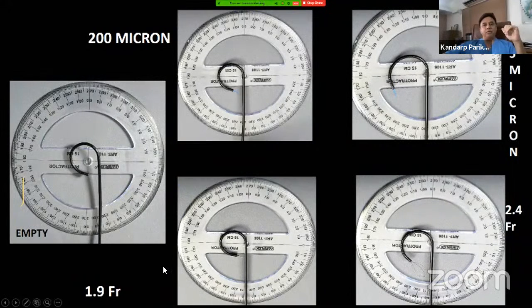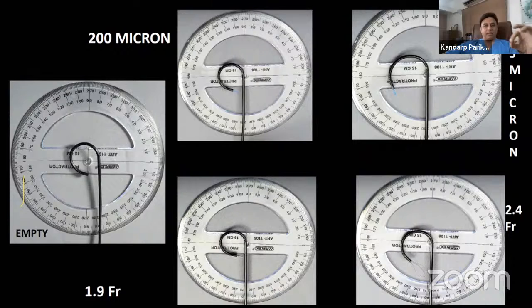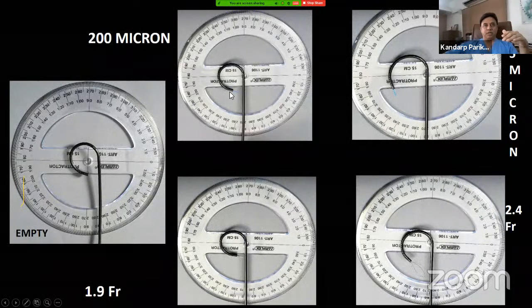Now, we discussed the accessory channel, which is 3.6 French in caliber. From the accessory channel, you can introduce water, as well as accessories like a basket or a laser fiber. When the accessory channel is empty, you can produce a 270-degree deflection like this. You can see it here. But the moment you put in a 200 micron laser fiber, the deflection is slightly reduced. There is a 20-degree compromise. So from 270 it has gone to 250, but that's not bad. You can still reach any lower calyceal stone with this position. You can see a small laser fiber coming out through the deflected tip of the scope.